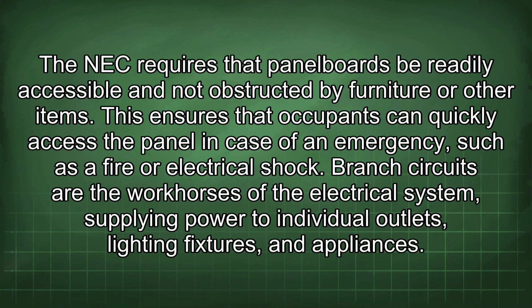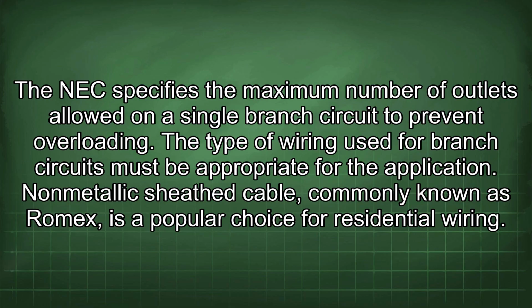The NEC requires that panel boards be readily accessible and not obstructed by furniture or other items. This ensures that occupants can quickly access the panel in case of an emergency, such as a fire or electrical shock. Branch circuits are the workhorses of the electrical system, supplying power to individual outlets, lighting fixtures, and appliances. The NEC specifies the maximum number of outlets allowed on a single branch circuit to prevent overloading. The type of wiring used for branch circuits must be appropriate for the application.